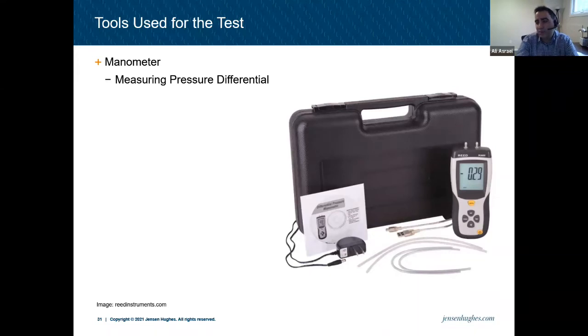Another tool we're using is a manometer. It's measuring pressure differential. As you can see, there are two spots here and here. These are the tubes. You add the tubes here. One of the tubes goes to the pressurized area and the other tube stays in the floor area. And it gives you a number here that you can read. And that gives you the differential pressure between the pressurized area and the adjacent floor area.